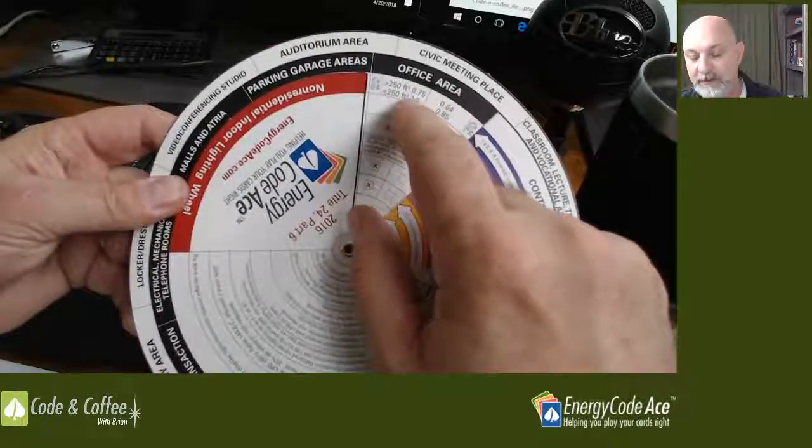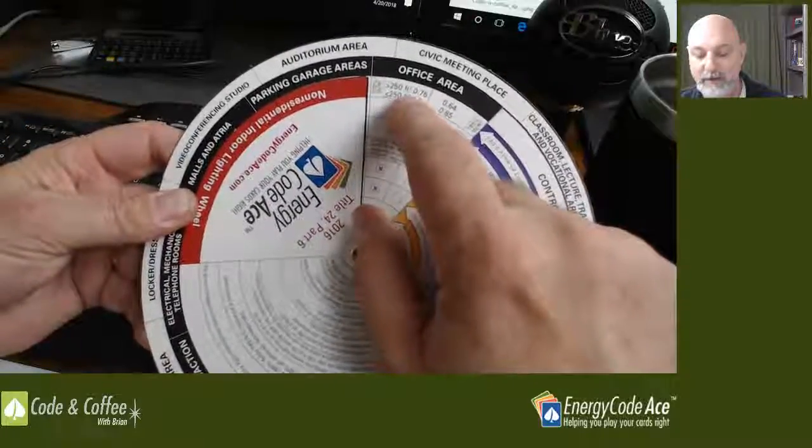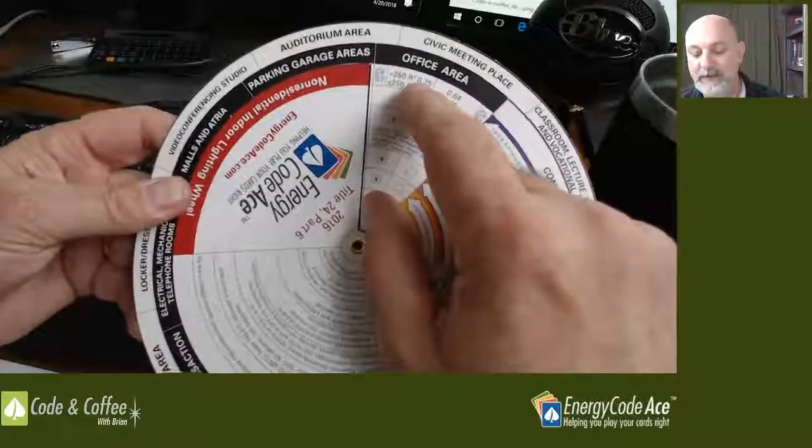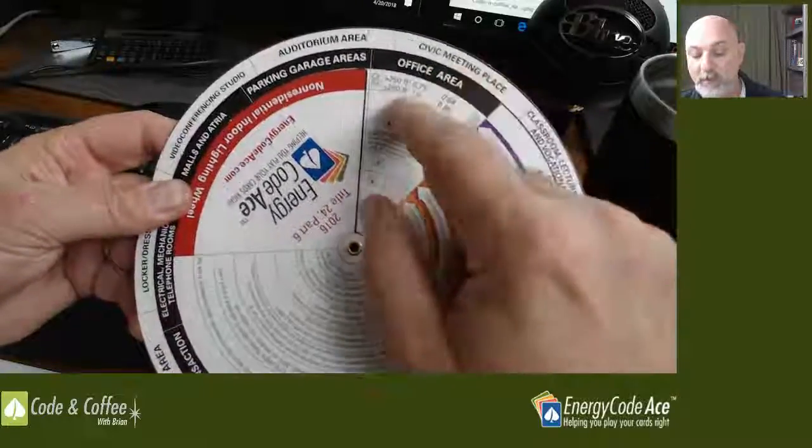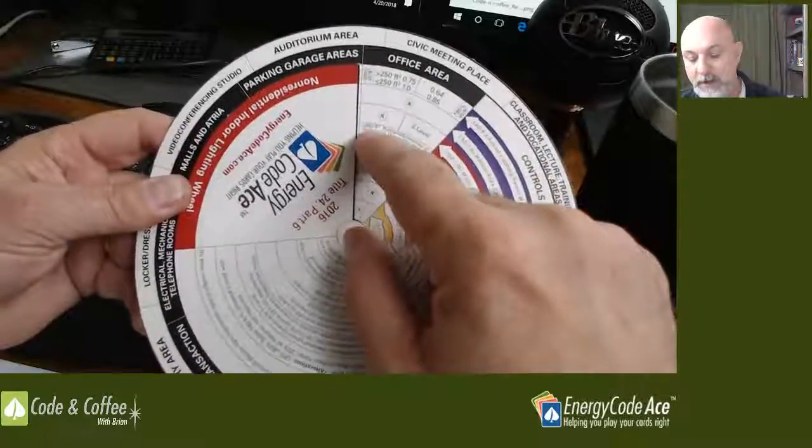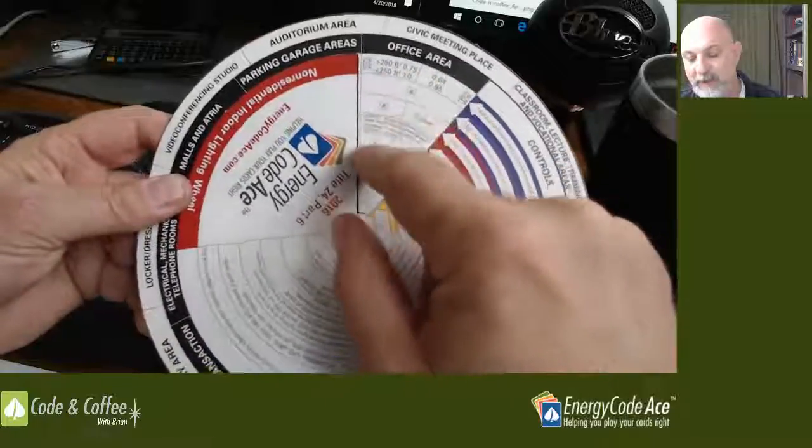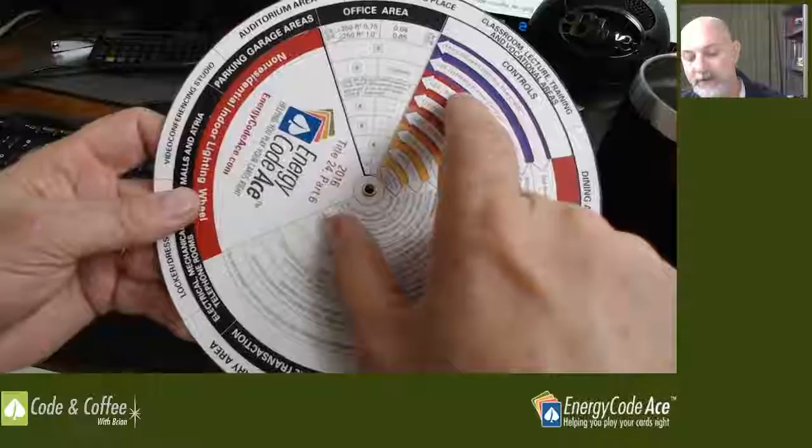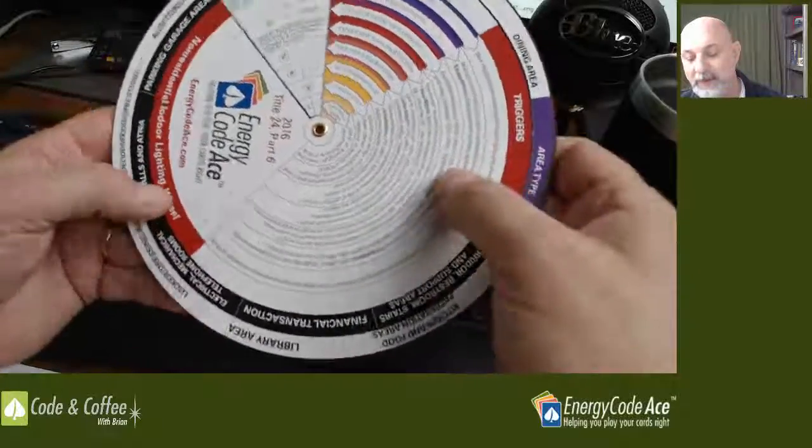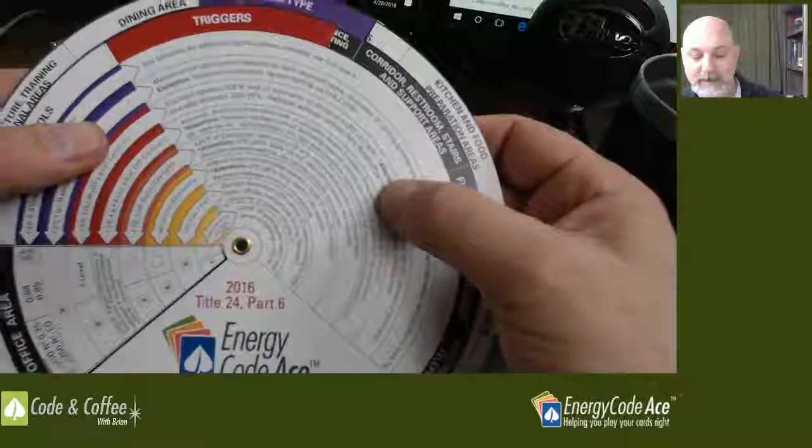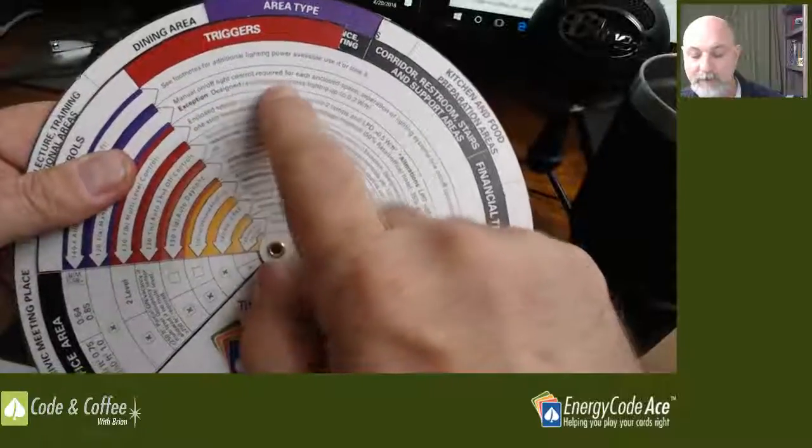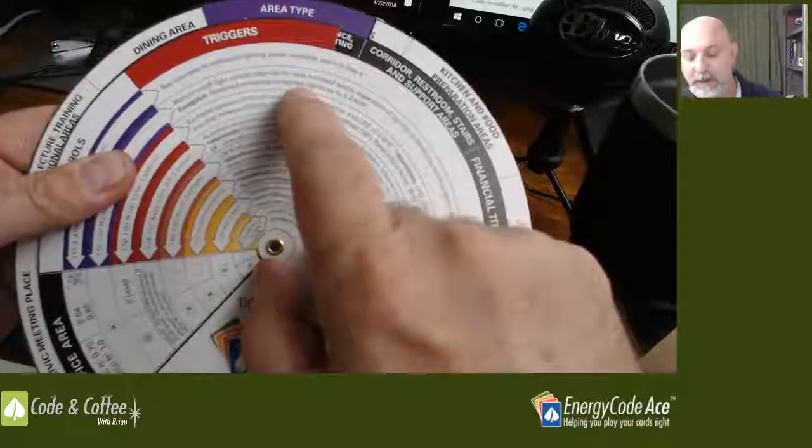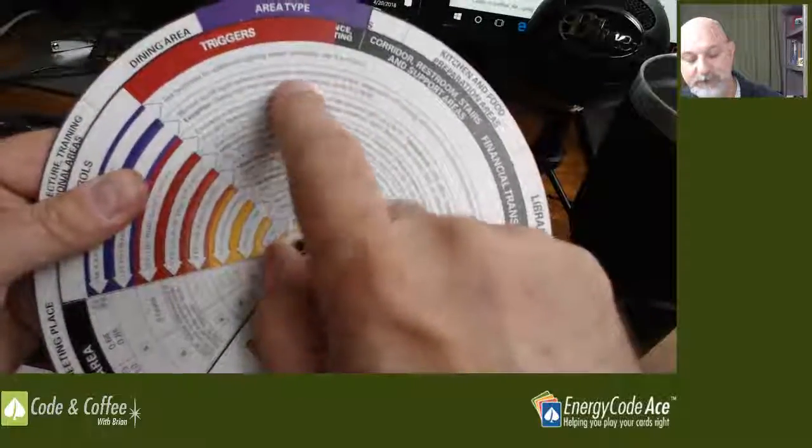Each of those have a different lighting power density. Greater than 250 is 0.75 watts per square foot. Less than 250 have a little higher allowance, one watt per square foot. If we're talking new construction or an addition, we're going to be on the left-hand side of this piece of pie here. We can see that manual area controls apply. We've got to have on-off switches located in the rooms. If we have certain exceptions here, depending on where that primary function area is or other requirements, we can apply one of those exceptions there. Take a look at those exceptions when you're reading this.